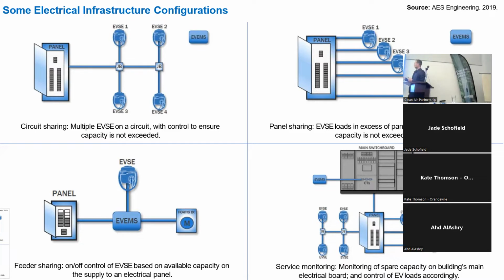Finally, a similar idea but in larger buildings is what we call service monitoring. If this was the schematicized electrical system for a large multifamily building, this is the service into the building, going through the transformer and into the main switchboard. You've got monitoring right there saying, yep, there's capacity, we're communicating to the EV charging, you're okay, you don't need to do anything. But if it's approaching capacity, say within 80% of the service's capacity into the building, it can communicate to the EV charging to start throttling down.